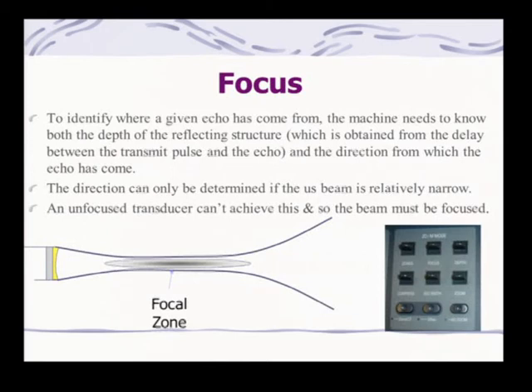Now the focus was what Tracy just showed you with that little arrow, and that's always important to move to either just below or on the organ that you're looking at. So whether it's a fetal heart or the gestational sac or a leg that you're trying to optimise. So that identifies where a given echo has come from, and the machine needs to know the depth of the reflecting structure. So the direction can only be determined if the ultrasound beam is relatively narrow. And all of these new transducers these days are actually focused. An unfocused transducer can't achieve this, and so you can't focus anything. We do get that on a lot of the older equipment that's been donated overseas. So sometimes if you're working on an outreach program, you might find some very, very old equipment.